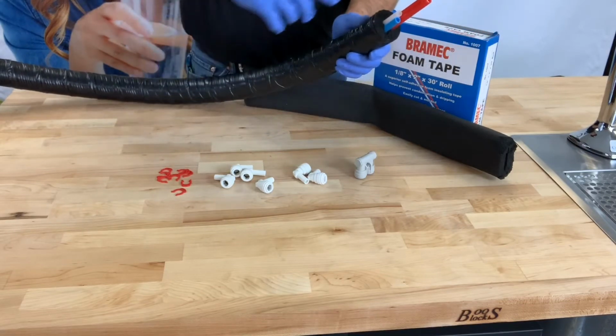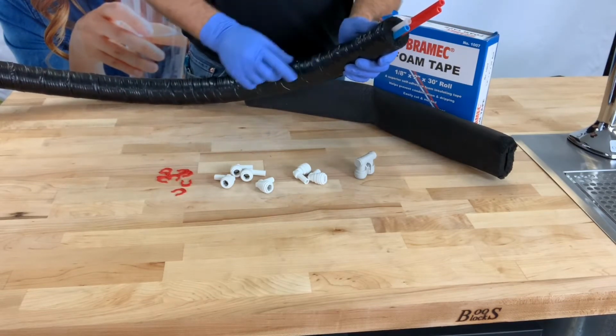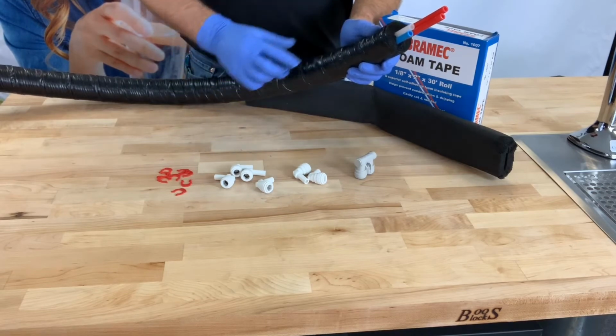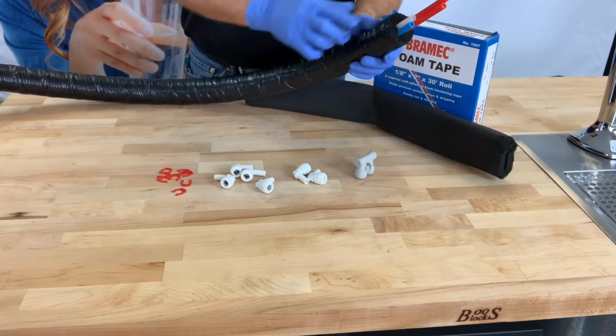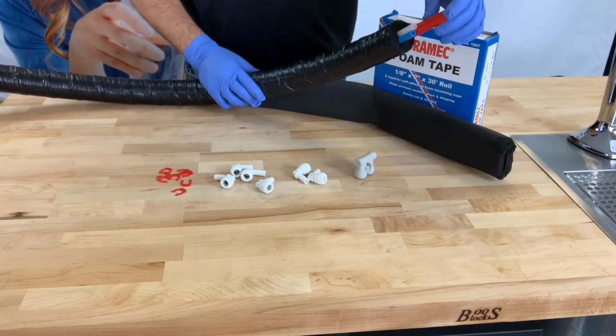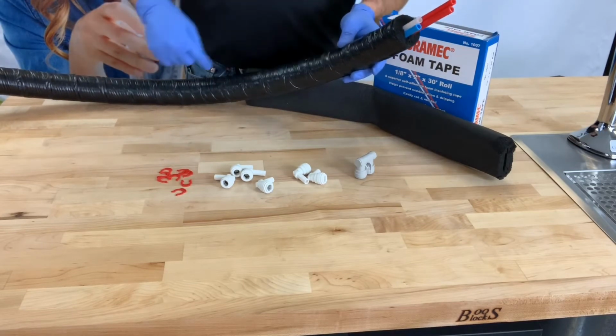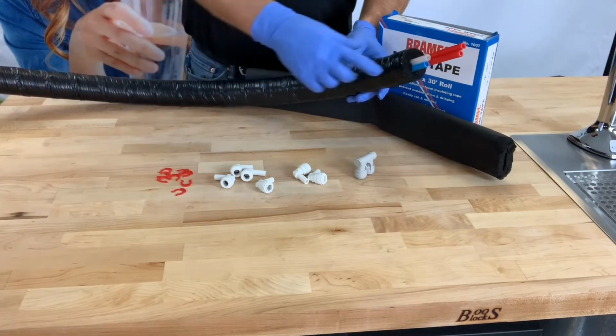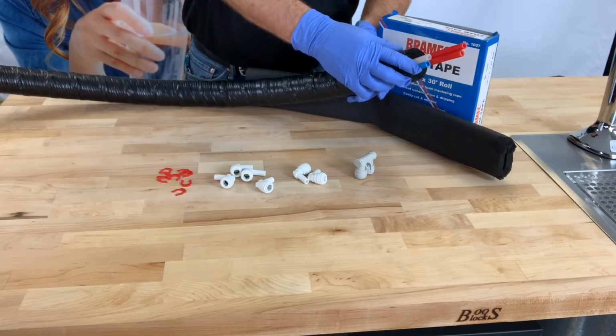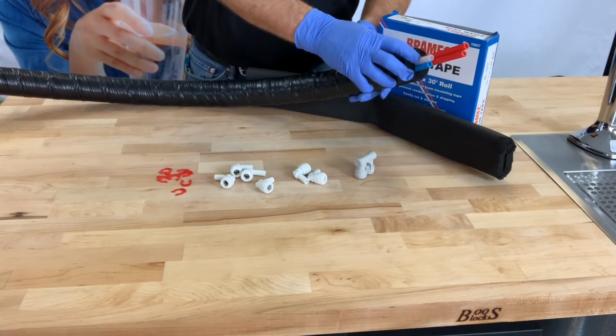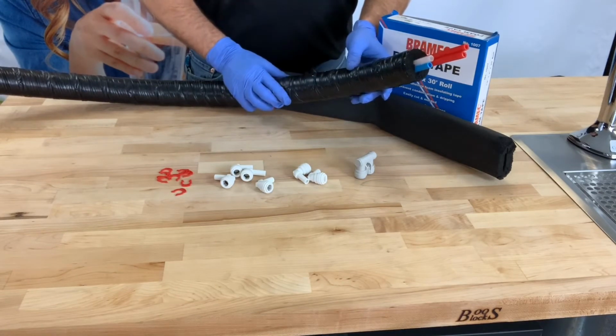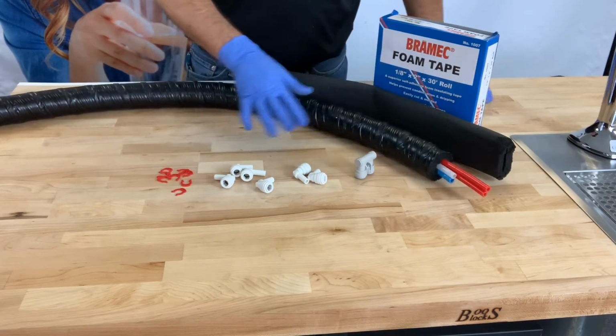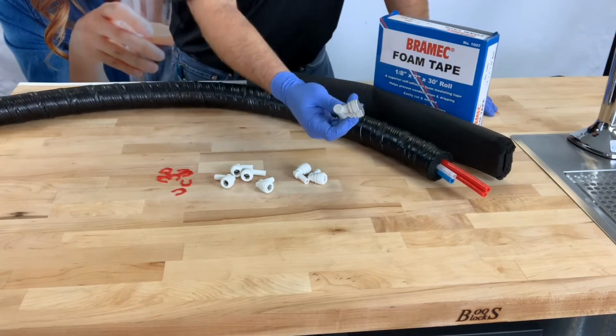I've cut back some of the lines. You'll see 2 red lines, a blue line, and a white line. The 2 red lines are your recirc line, one outgoing and one return. The blue line is your sparkling water, and the white line is your still chilled water. Out here on the cabinet I've got this U-bend.